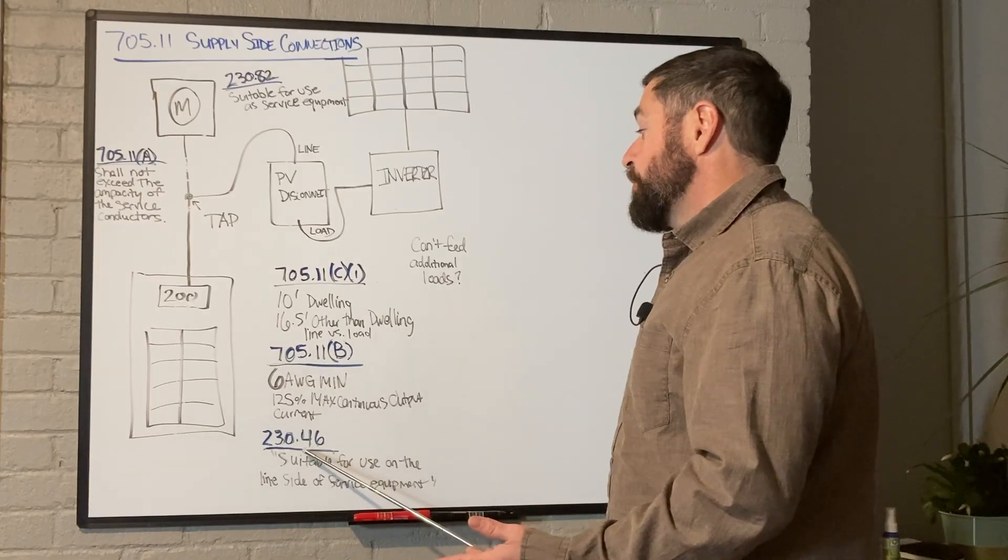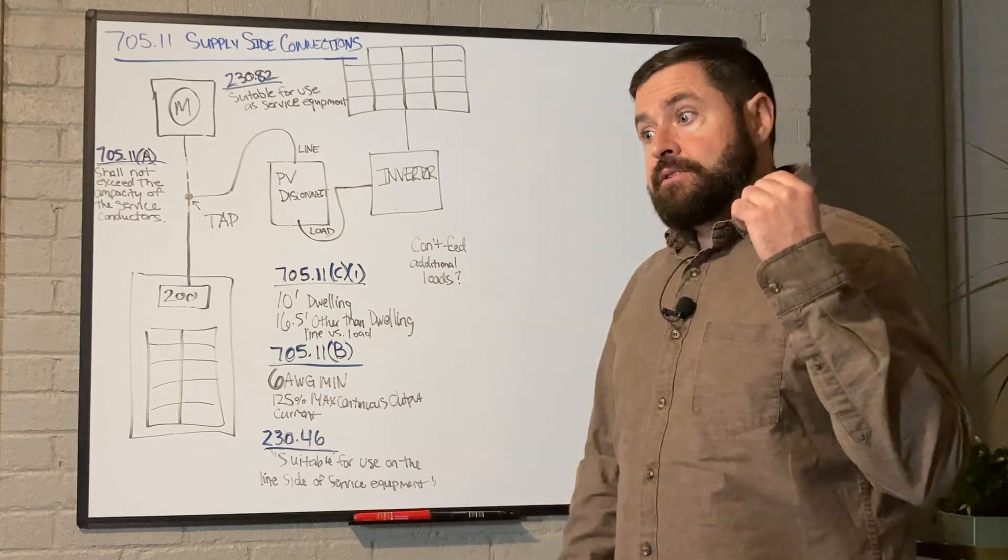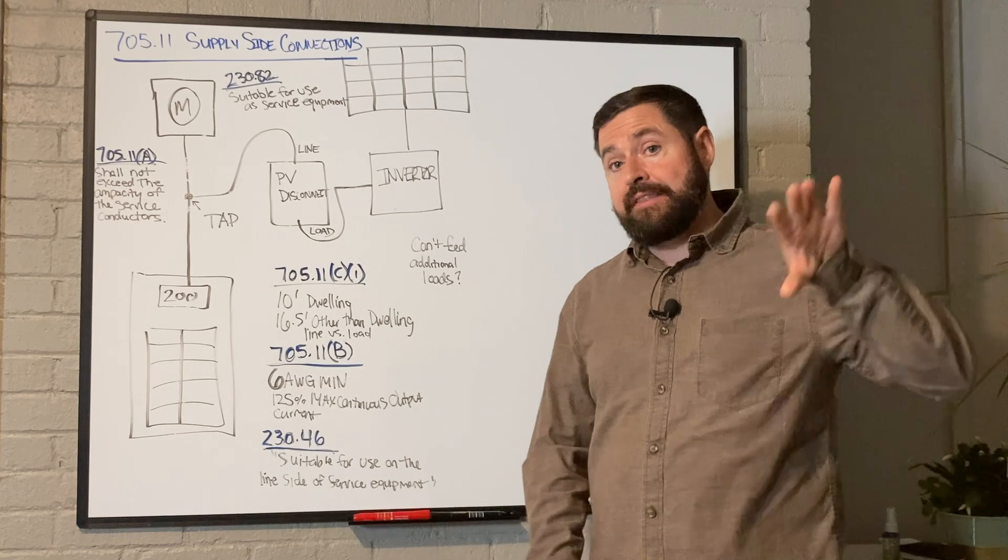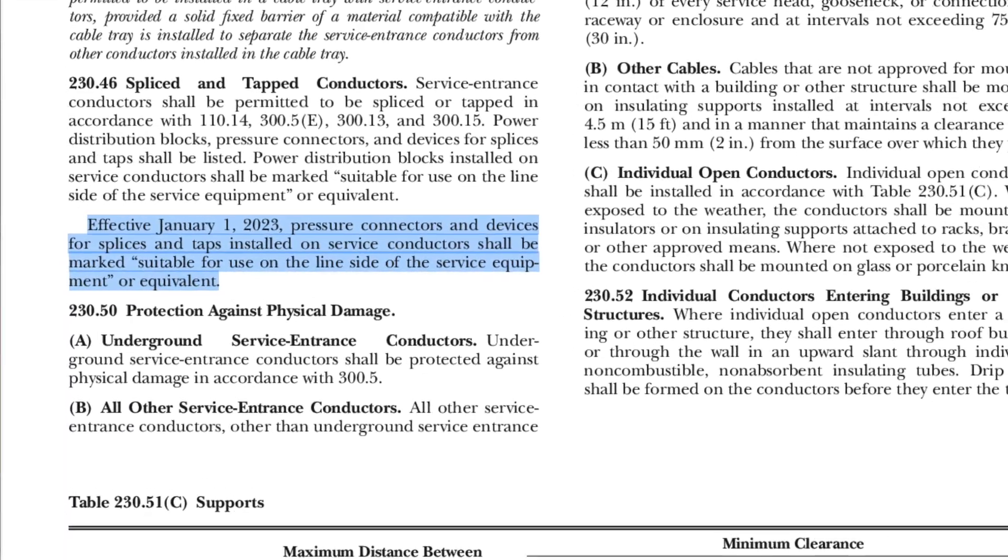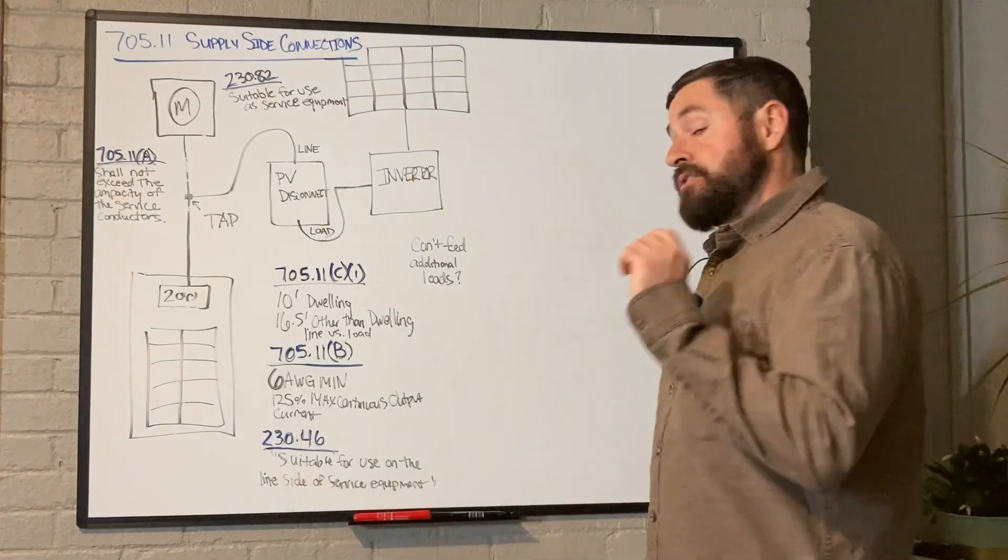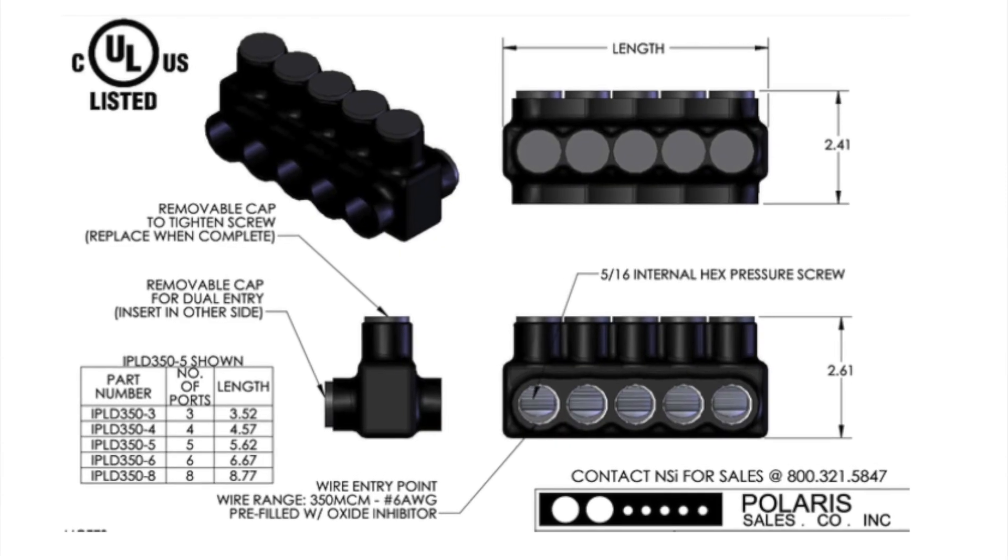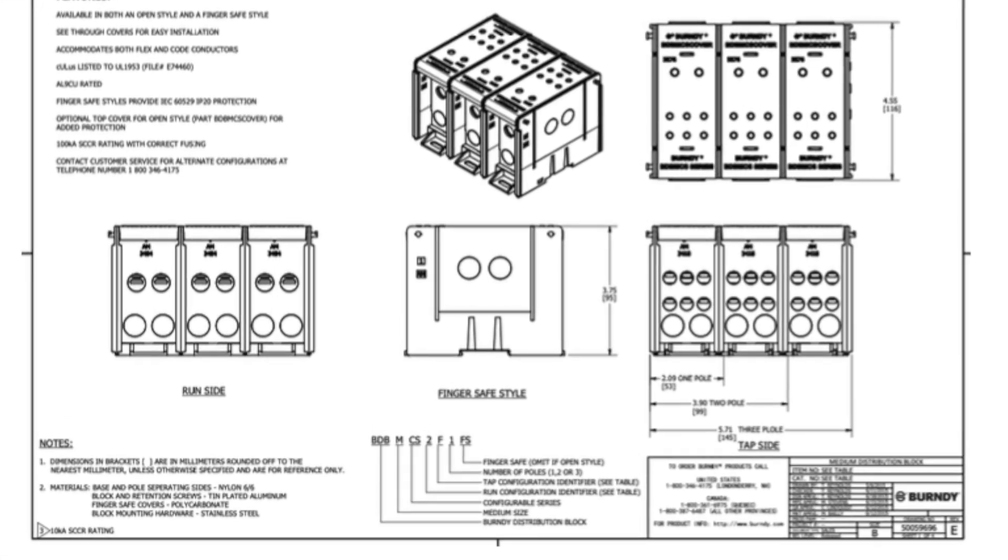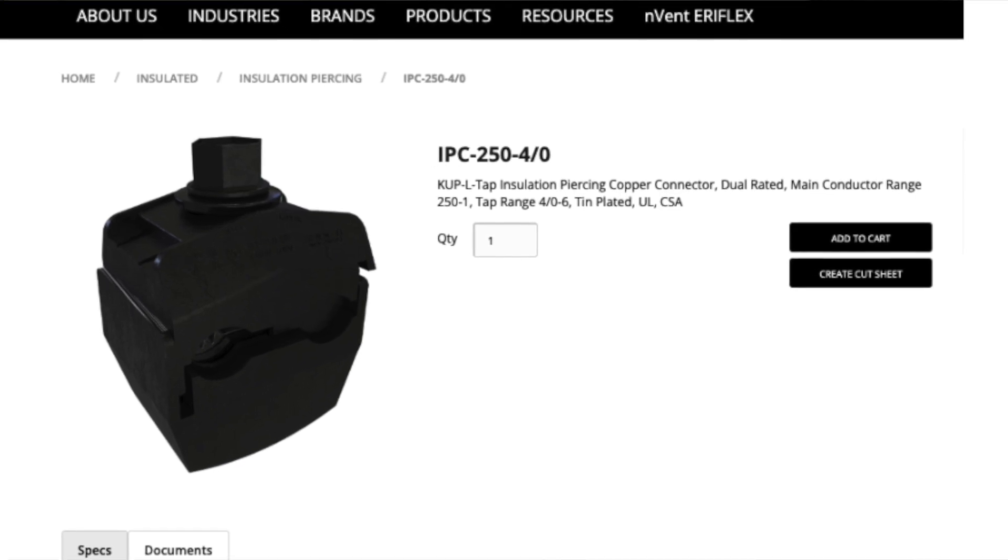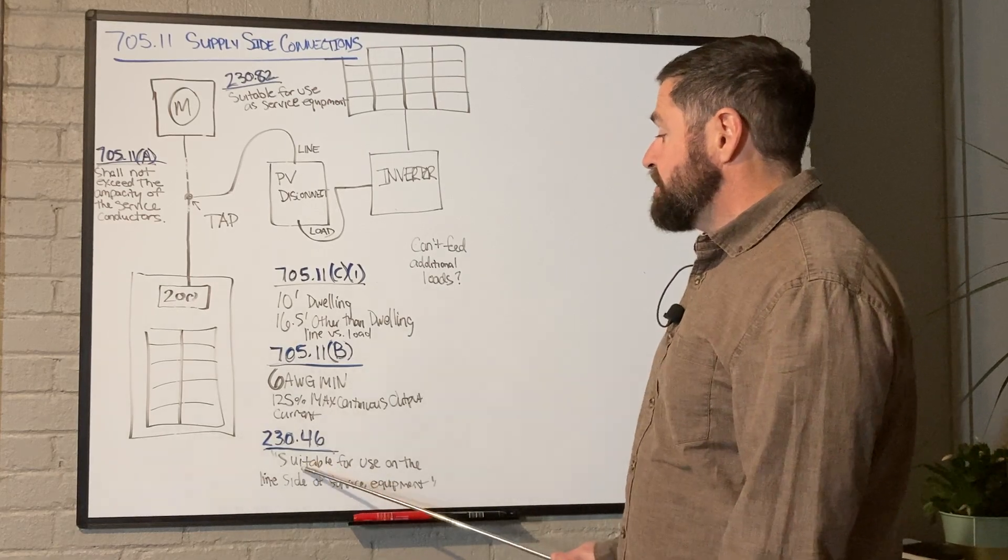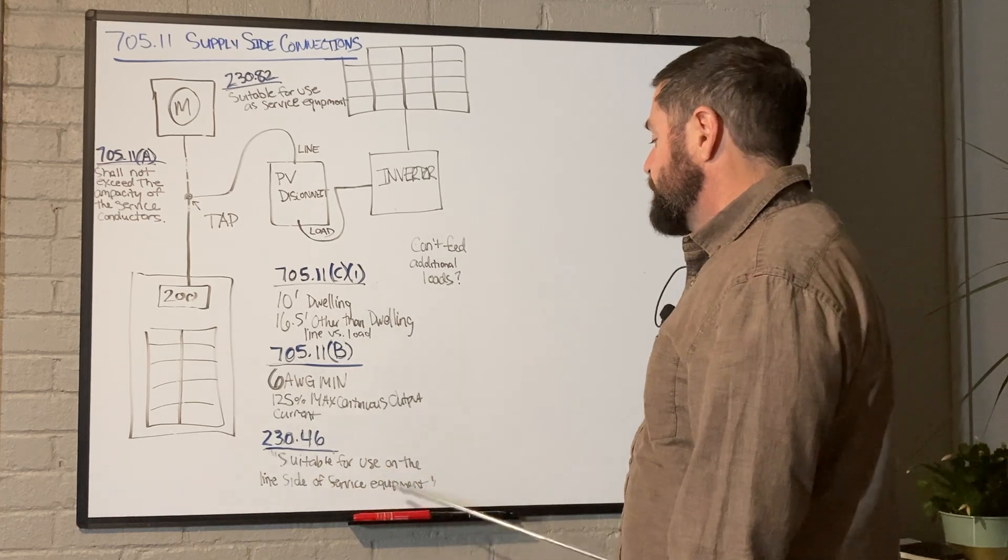Next, we've got 230.46. As of January 1st of 2023, this is in the 2023 National Electric Code, they put this stipulation in there that your tap connectors - whether that's going to be a polaris lug, distribution block, piercing tap connector, whatever it is - it has to state on the connector that it is suitable for use on the line side of the service equipment.